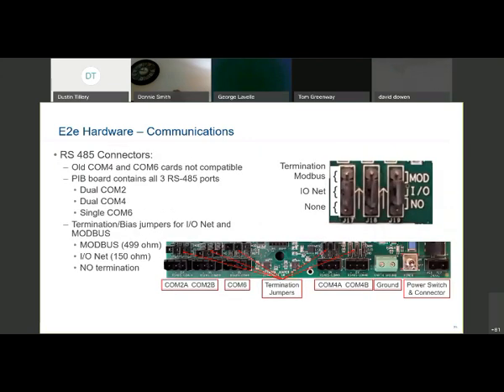All right, down at the bottom of the new E2e PIB board is where you're going to find your COM loops, your COM2A, 2B, 4A, 4B, COM6, as well as your termination jumpers. Guys, I cannot express this enough. Please, if your technicians out in the field are having communications issues, the very first thing they should check is termination. Make sure that that COM loop is terminated.